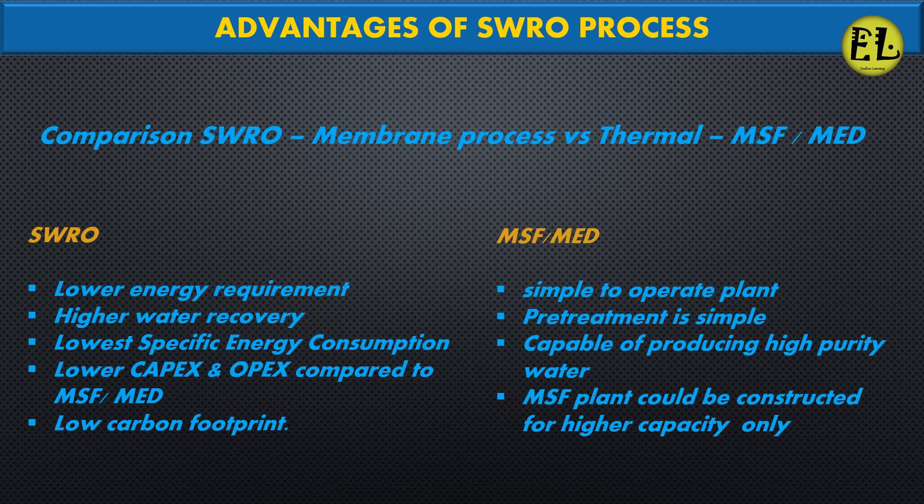Comparison — SWRO Membrane Process versus Thermal MSF/MED: SWRO offers lower energy requirements, higher water recovery, lowest specific energy consumption, lower capex and opex compared to MSF/MED, and a low carbon footprint. MSF/MED is simple to operate, requires simple pre-treatment, is capable of producing high-purity water, but MSF plants can only be constructed for higher capacities.